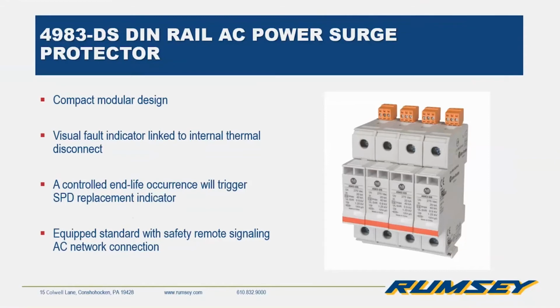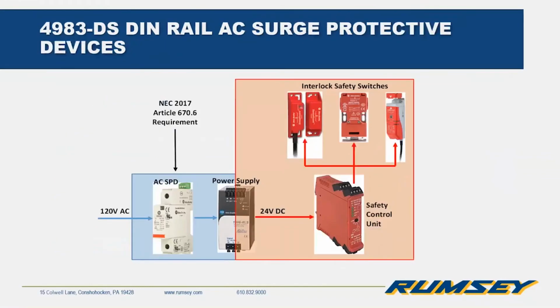And essentially, we stock these here at Rumsey, and they are available on short notice. There are some new changes to the NEC that have added some additional requirements to using surge protective devices. So here's an example of how one of these would be used with some interlocks or safety switches. Essentially, it would go before the power supply, and it would protect those components from a surge. Typically, Rockwell and anyone who manufactures these would promote a cascaded approach, which means you would have various surge devices upstream all the way to downstream in the panel, protecting those individual loads. You want to make sure that you have the ability to clear that surge when it hits from various angles.